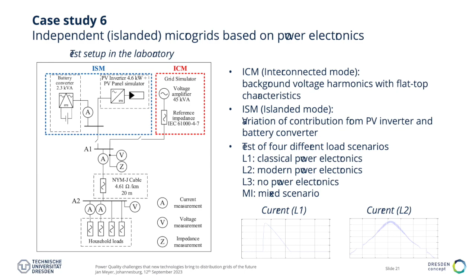Let's look at the results in terms of harmonic voltages and currents at the connection point of those loads, focusing on the first two scenarios. With classical line-commutating equipment, the lighter red shows islanded mode and the darker one shows interconnected mode. The harmonic emission is clearly higher in interconnected mode, so you might think the emission is lower and better in islanded mode.